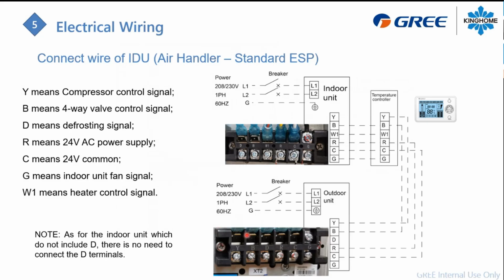So we saw here the connection for the outdoor unit. You have your thermostat into it, and then this is an example of your indoor unit if you have an electric air handler. So again, you have a D terminal right here. If you need to use it, you will connect the D to the D. You have a B terminal for your reversing valve, W1, RC, and now the G terminal is for the call for the blower. So in that case, the G terminal is in use when you have an electric air handler.